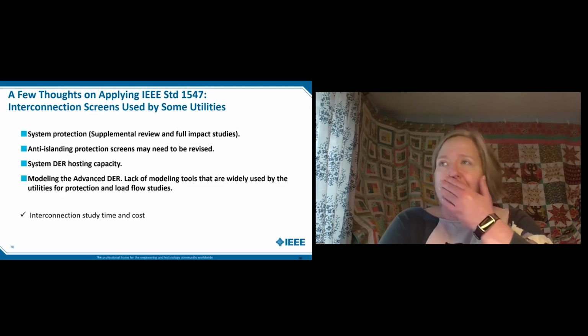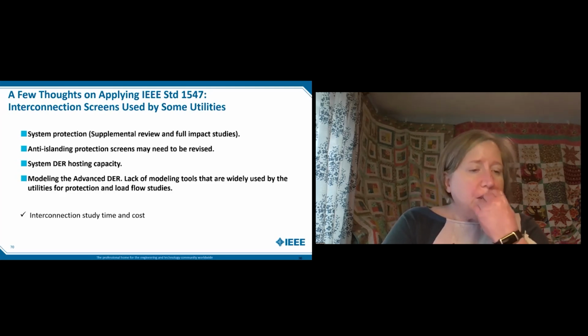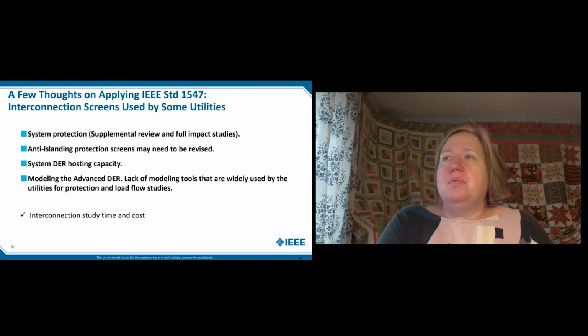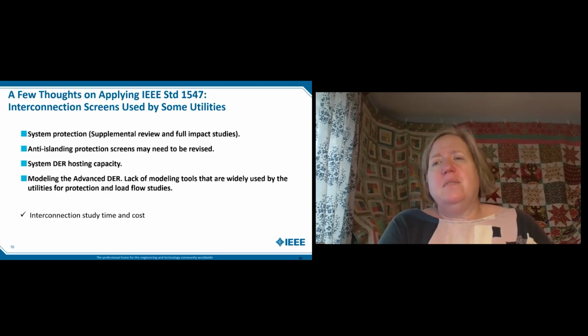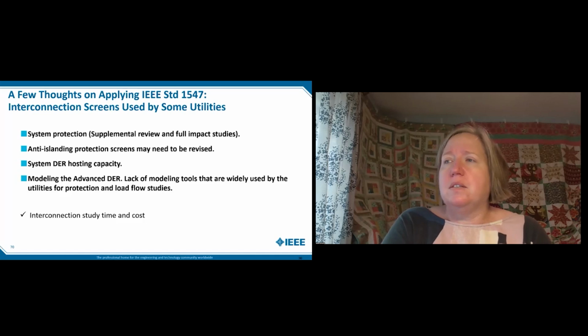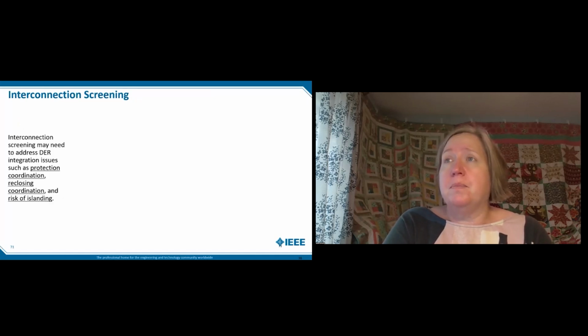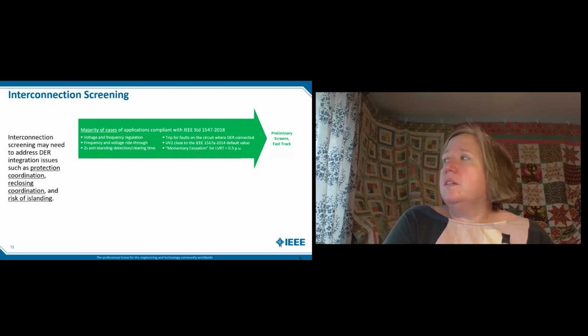So there are some utilities that use screens, looking at the protection, the anti-islanding, the hosting capacity, and the fact that we still don't have the best models for looking at advanced DER and running through everything it does. And there's time associated with doing these studies. Interconnection screening looks at the DER integrations such as protection coordination, reclosing coordination, and risk of islanding. You have a lot of them that we can pretty much wave through. They meet all the requirements. They're small enough that they don't cause a problem.